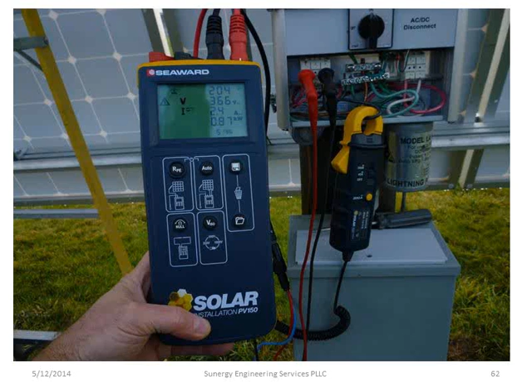This is a 2400 watt array, which is pretty low, but there's only 200 watts of irradiance. Most of these meters, when the irradiance drops below 100 watts per meter squared, won't even take a recording. For commissioning, they recommend testing at 800 to 1200 watts per meter squared, in the middle of the day.